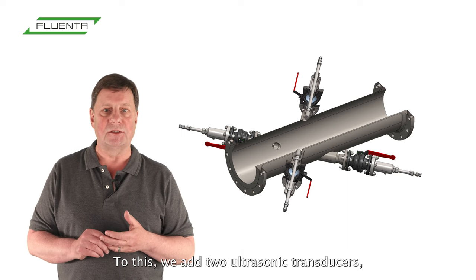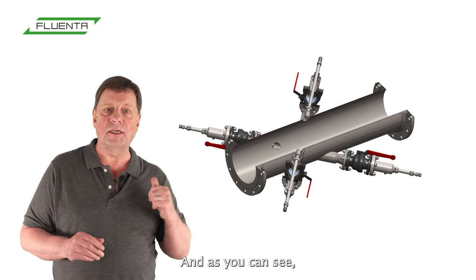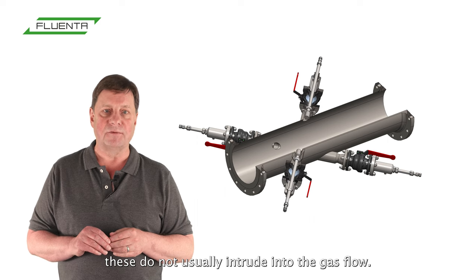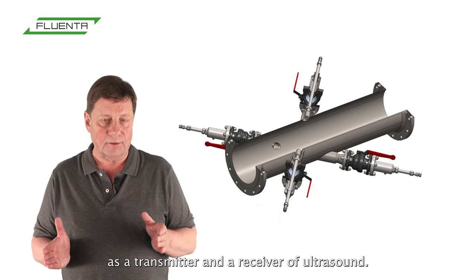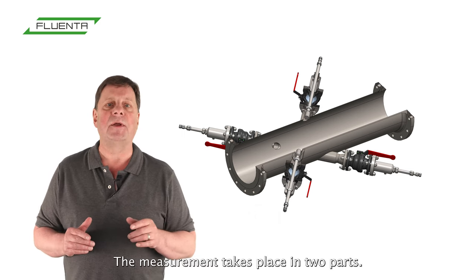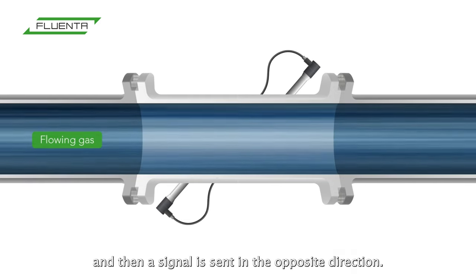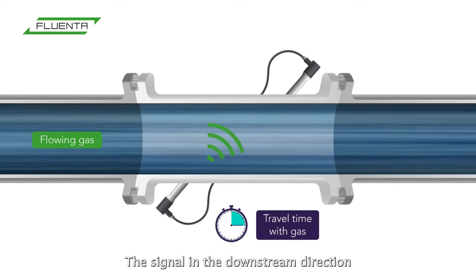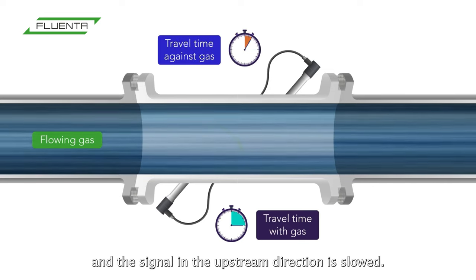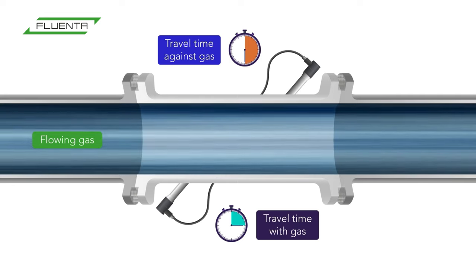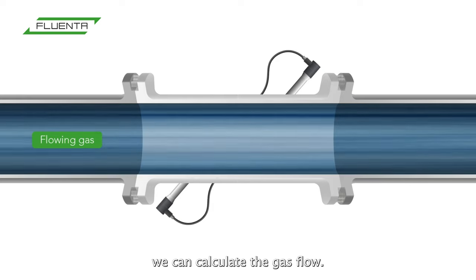We add two ultrasonic transducers, which are typically angled at 45 degrees to the direction of the flow. As you can see, these do not usually intrude into the gas flow. Each transducer can act as a transmitter and a receiver of ultrasound. The measurement takes place in two parts: first, a signal is sent from one transducer to the other, and then a signal is sent in the opposite direction. The signal in the downstream direction is speeded up by the gas flow, and the signal in the upstream direction is slowed. We measure the time of flight for each of these signals, and from those measurements we can calculate the gas flow.